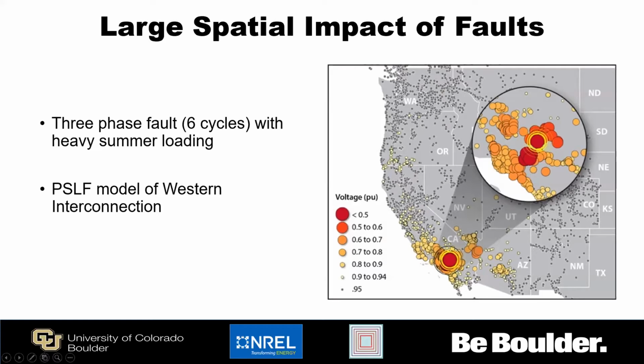So here we're looking at a model of the entire Western interconnection of the United States, and we have a fault here at Lugo, which is in Southern California. And we can see there are areas, even all the way up into Oregon and Washington, where we see voltages that are now below standard levels from a fault that's thousands of miles away. And so this is very important that we can understand not only the impact of these faults in multiple locations, but the impact on the distributed generation that is then connected in those locations.